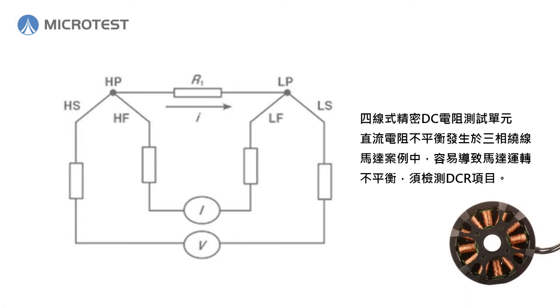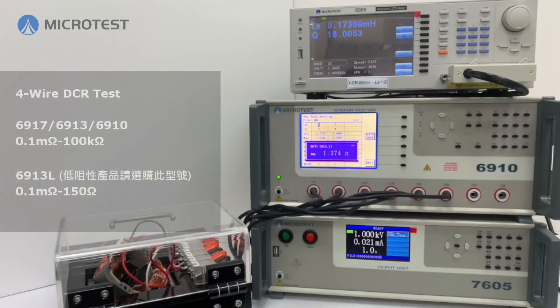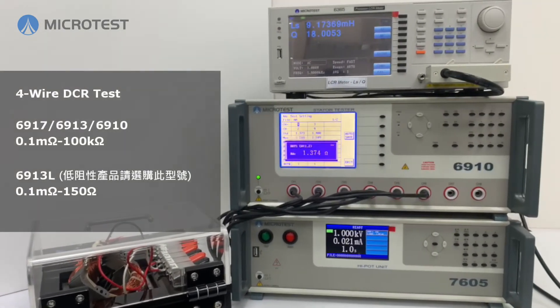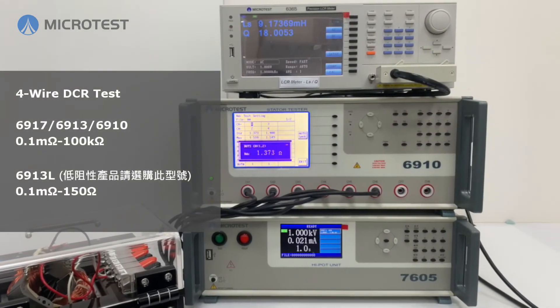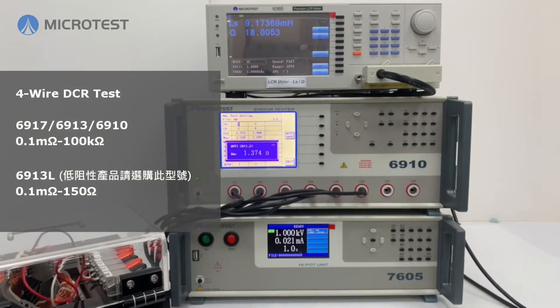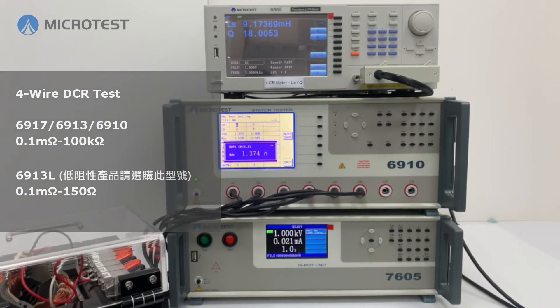Uneven DC resistance can occur in a 3-phase motor, which will cause uneven rotation. Microtest's 4-wire DC resistance measurement will be more accurate than other methods.